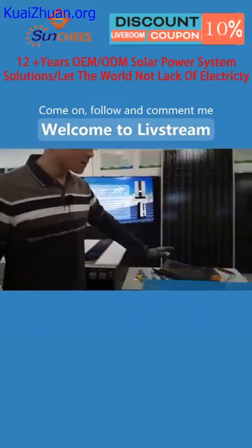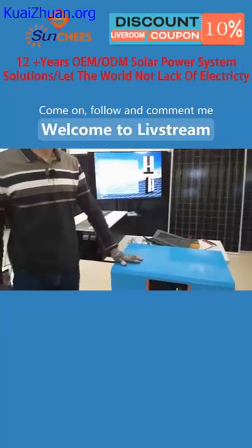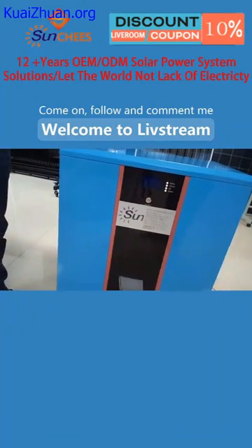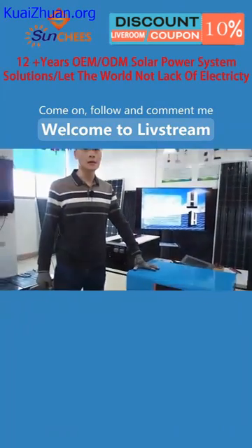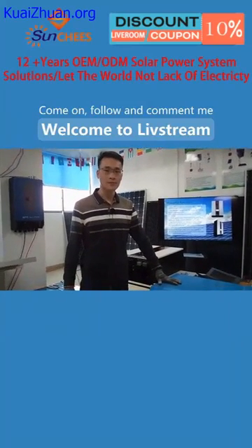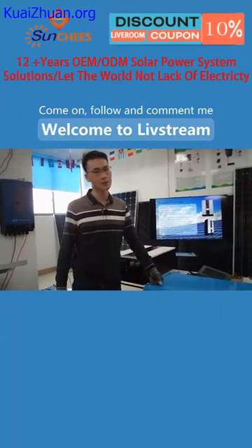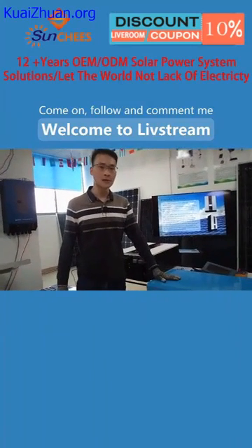And the fourth part will be the battery bank. Before, we were using gel battery or lead acid battery to make the complete set solar power system. But now we are using LiFePO4 lithium battery, because it has big advantages. The lithium battery bank's lifespan is more than 8 years, and the deep discharge cycle count will be more than 2,000 times. That means the lifespan and deep cycle count are much longer than the gel battery. That is why we are using the lithium battery to make the complete set solar power system.